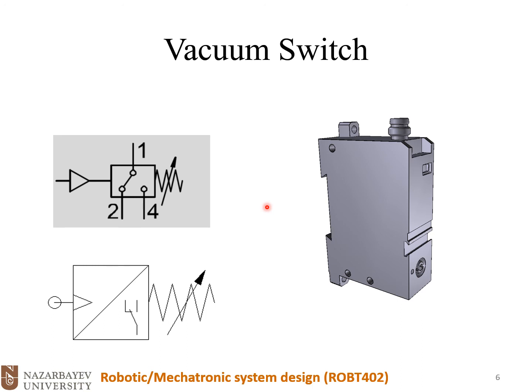through the suction cup into the circuit. So the vacuum pressure will drop, and the part will drop in the middle of the way. So we don't want that to happen. So we need to measure the vacuum pressure, and once the vacuum pressure reaches the desired one, the vacuum switch will stop the flow of air into the Venturi, or will shut the 2x2 directional valve.